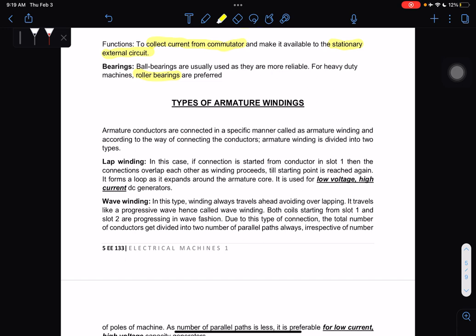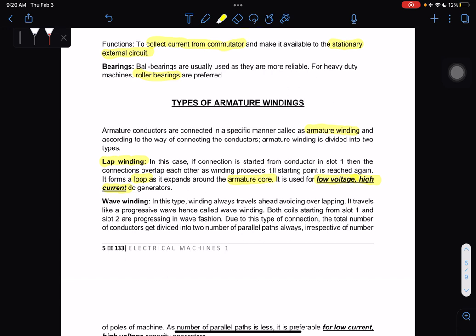Armature conductors are connected in a specific manner called armature winding. According to the way of connecting the conductors, armature winding is divided into two types. First, we have lap winding. In this case, if connection is started from a conductor in slot one, the connections overlap each other as the winding progresses until the starting point is reached again. It forms a loop as it expands around the armature core. It is used for low-voltage, high-current DC generators.